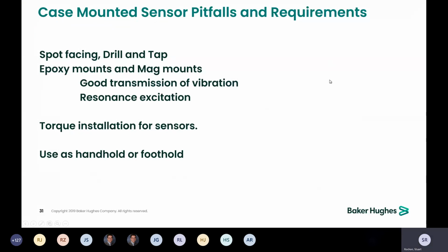Some of the requirements and pitfalls: spot facing, drill and tap is the most recommended method of mounting. Some sensors do have a pipe thread so that they don't need a spot face, but you still have to drill and tap. We also see epoxy mounts and mag mounts a good bit. Make sure that you use an epoxy that gives you good transmission of the vibration, a good rigid epoxy. If it's a softer, gummier epoxy, it can actually damp your vibration.